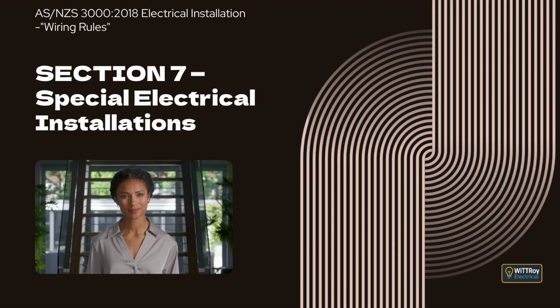It explains that socket outlet earth contacts must be connected to this equipotential bonding conductor, and that any designated protective earthing conductor and supply cables or flexible cords to equipment, other than Class II equipment, must also be connected to the equipotential bonding conductor. It explains that exposed conductive parts of the source of supply that are earthed must not be simultaneously accessible with exposed conductive parts of the separated circuit. It also explains that a protective device must disconnect the separated circuit automatically if two faults result in exposed conductive parts becoming connected to live parts of different polarity.